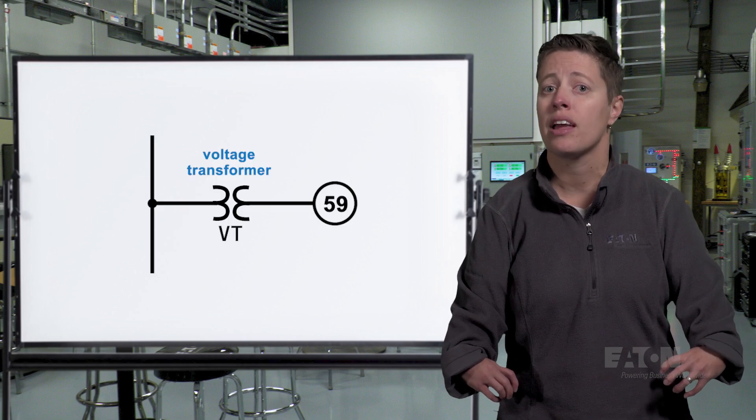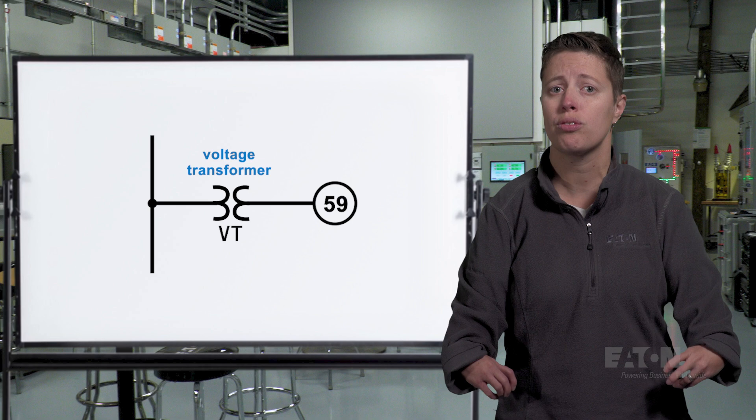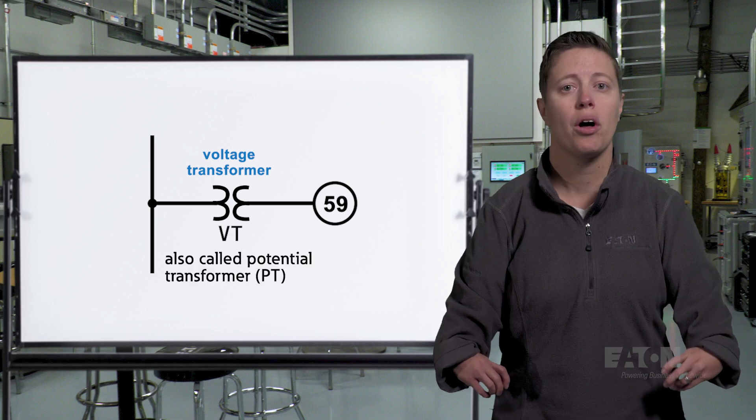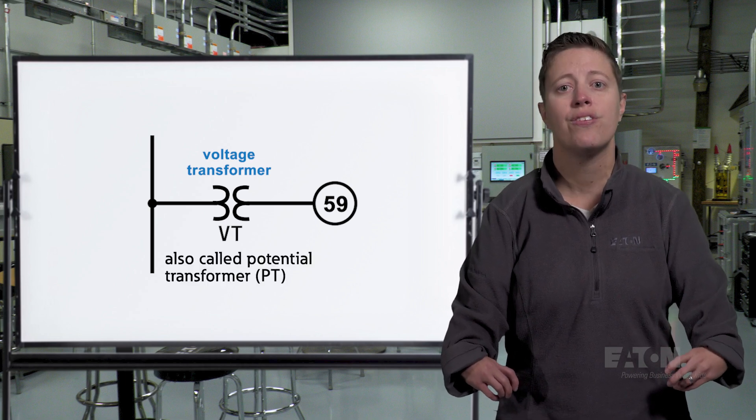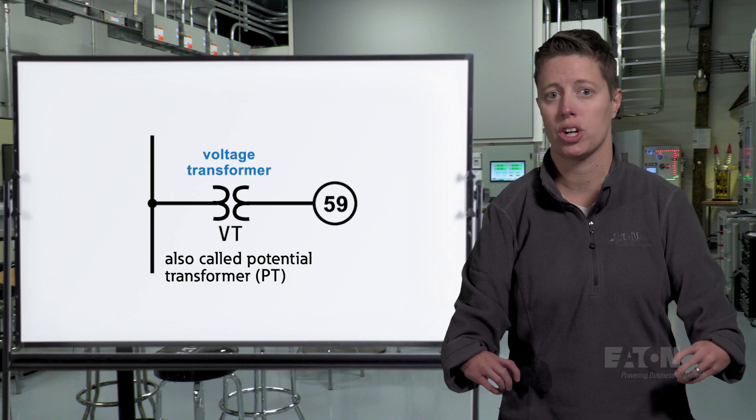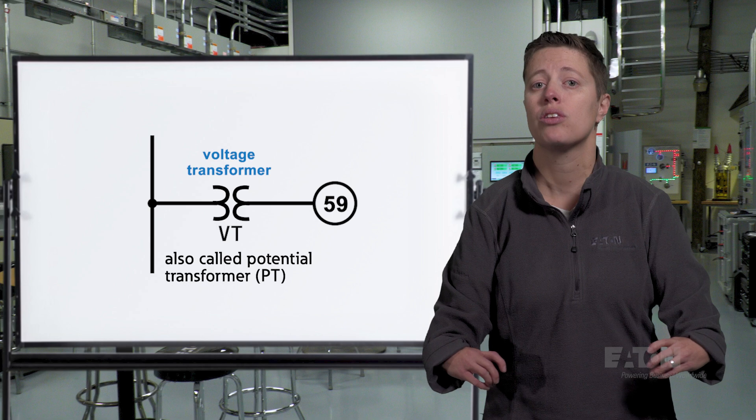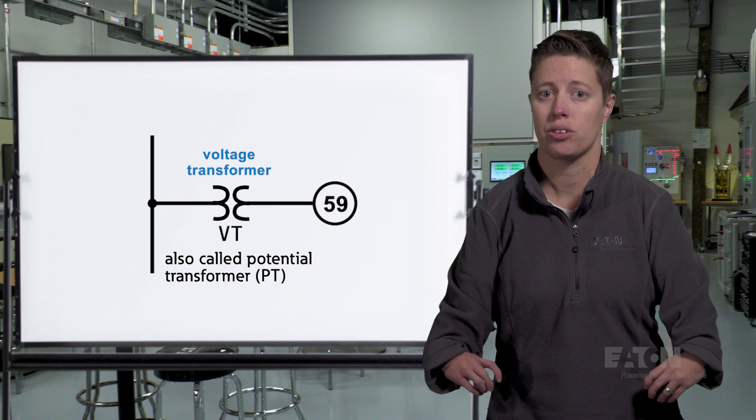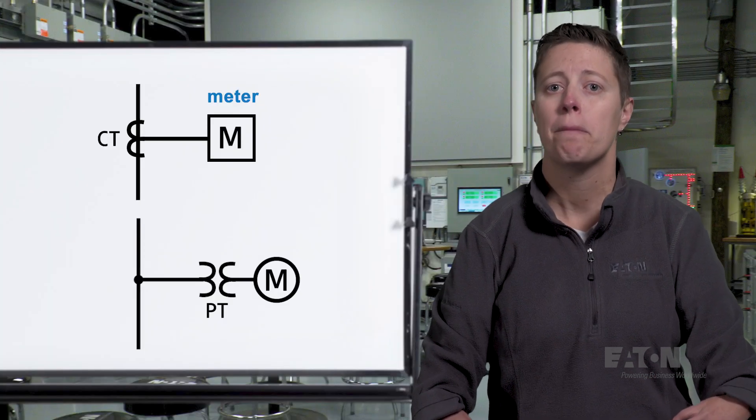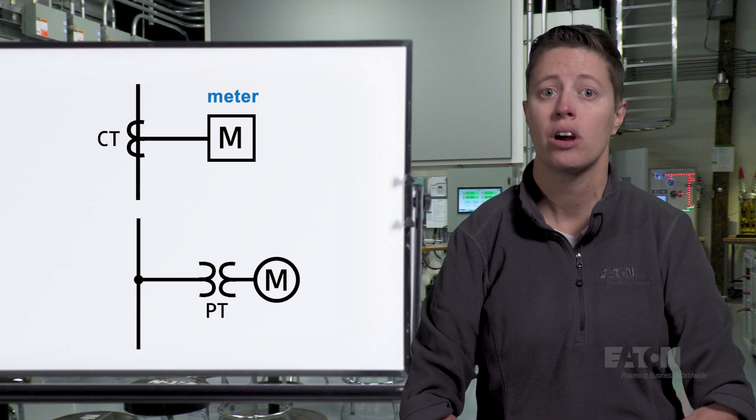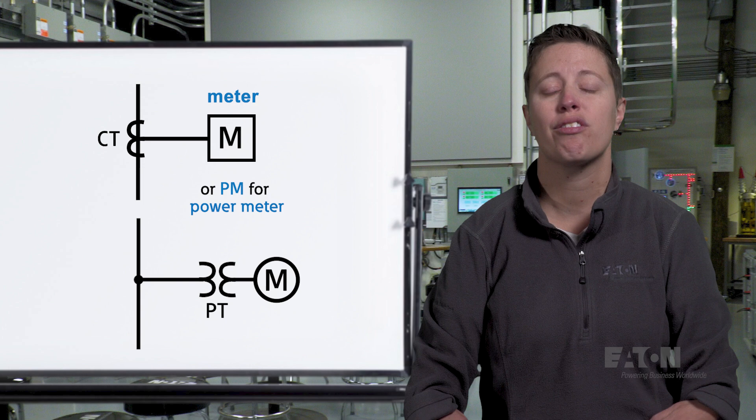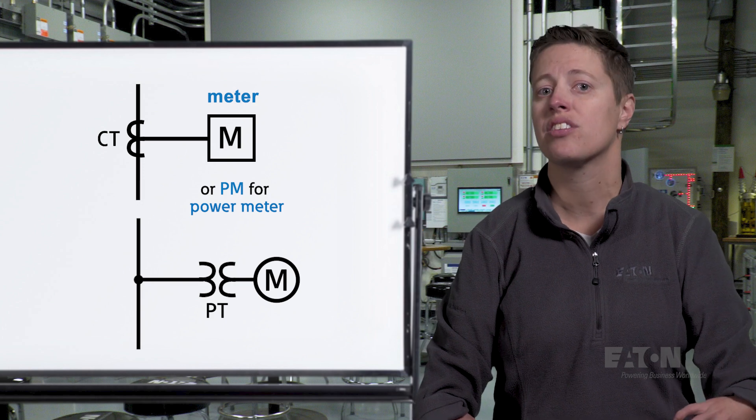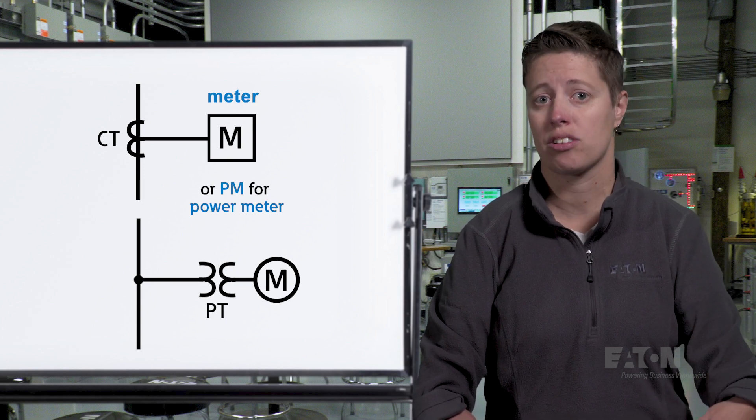Similarly, you may see relays or meters fed by a smaller version of the transformer symbol we discussed earlier. This is a voltage transformer or VT, also called a potential transformer or PT. Its function is like the current transformer but for voltage. The VT takes line voltage and transforms it to a lower voltage to be safely read by devices like protective relays or meters. Speaking of meters, a power meter may be shown with an enclosed M for meter or PM for power meter extending from a CT or PT similar to a protective relay.